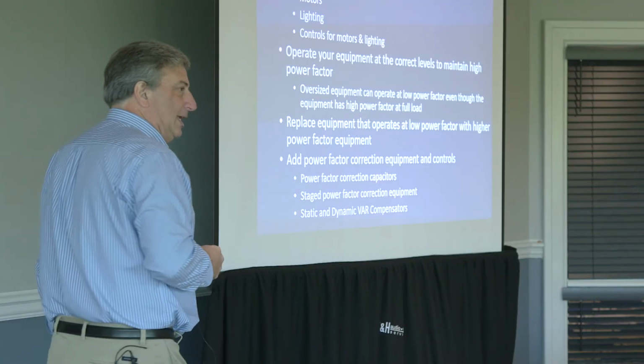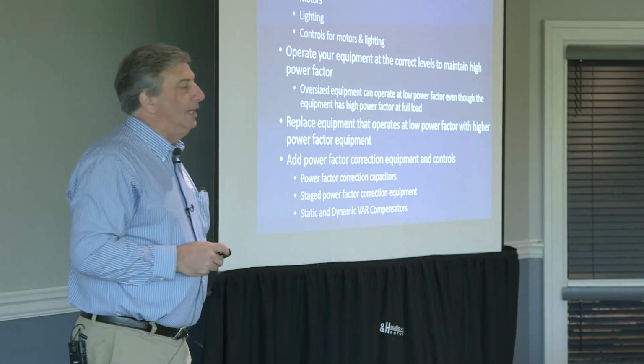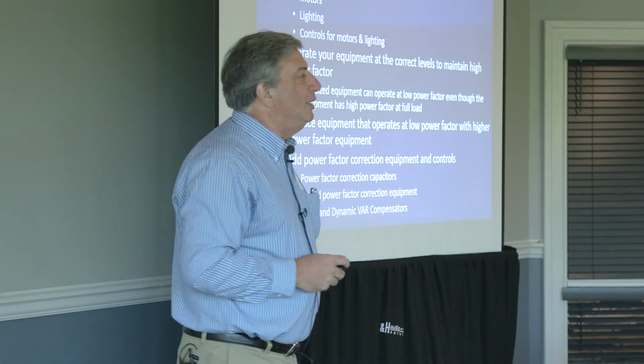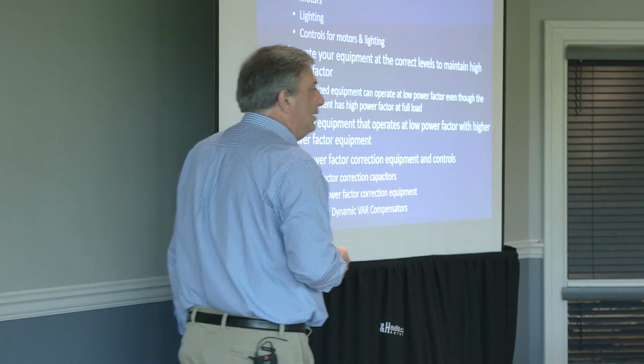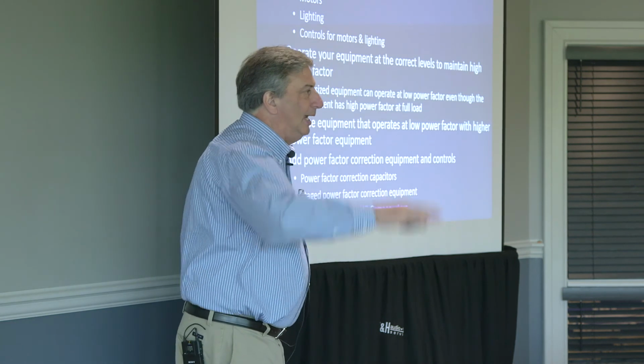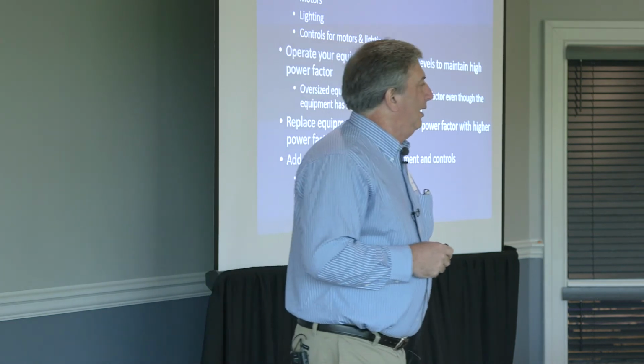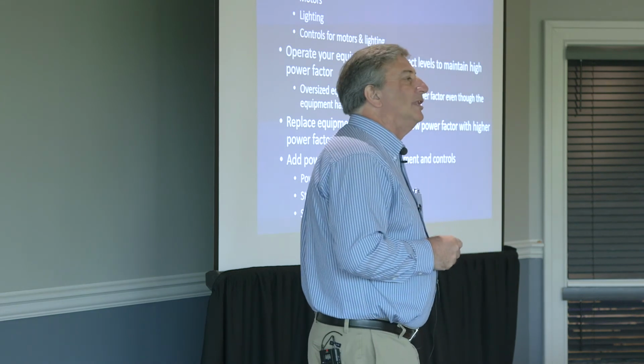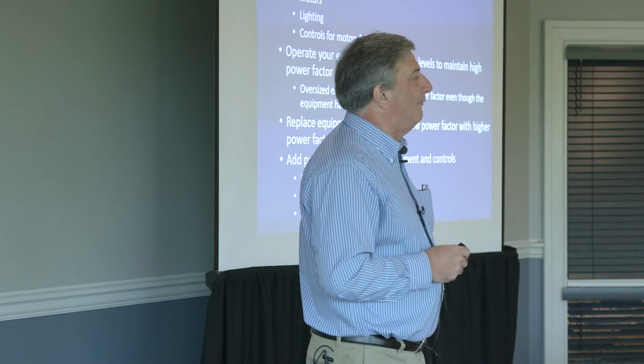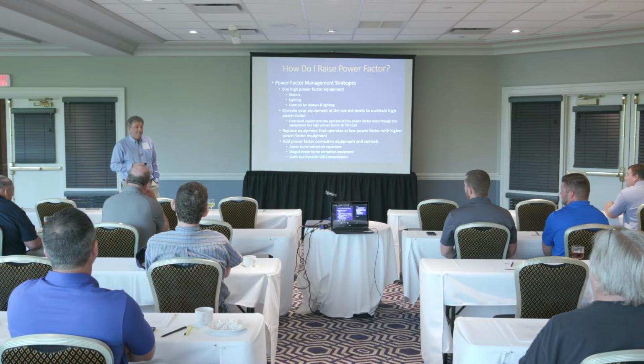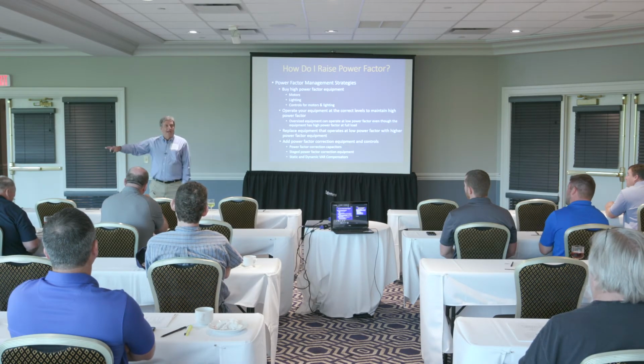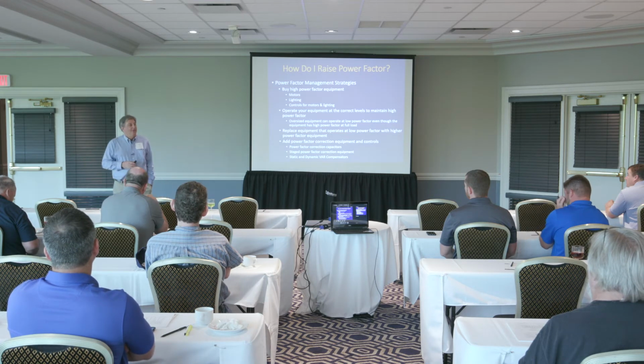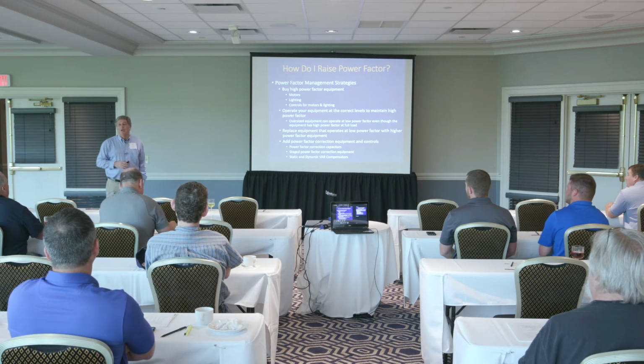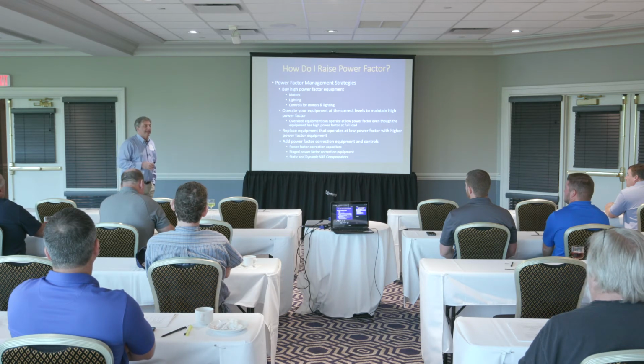I saw a retrofit done in another state here recently where the company got a big LED rebate check from the utility, and then they were screaming because their power factor at their plant went way down. We started asking questions and looking at specs, and they had put in LEDs with a 32% power factor. And those LEDs run all day long, right? So we'll talk more later. You can get some really crappy power factor LEDs out there. They're imported. You can probably guess from where mostly.